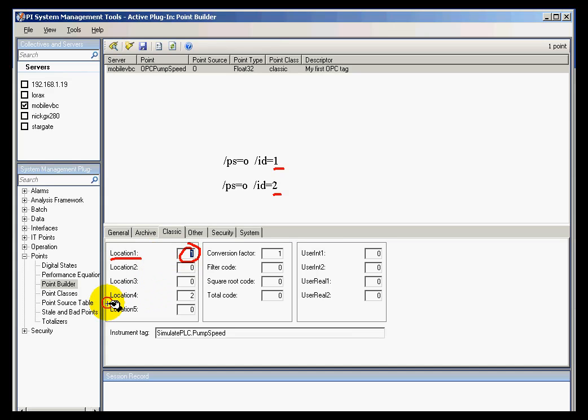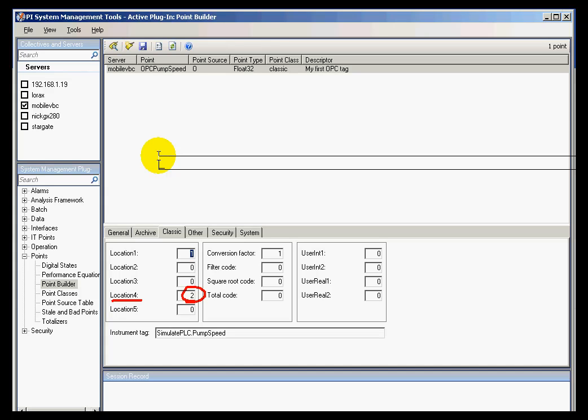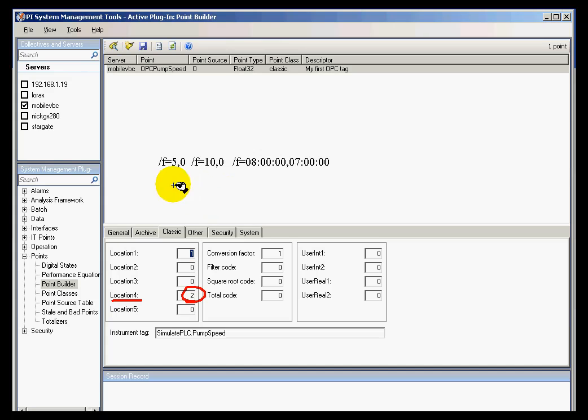Now location code 4 is a second very common usage. It's the scan class. As we mentioned earlier, scan class is identified when you start up the interface with the /F parameter. If we look at a typical interface startup, I say /F=5 seconds at every 0 second, and /F=10 seconds at the 0 seconds, and /F= let's go with 8 hours, offset 7 hours from the start. These are three different scan classes.